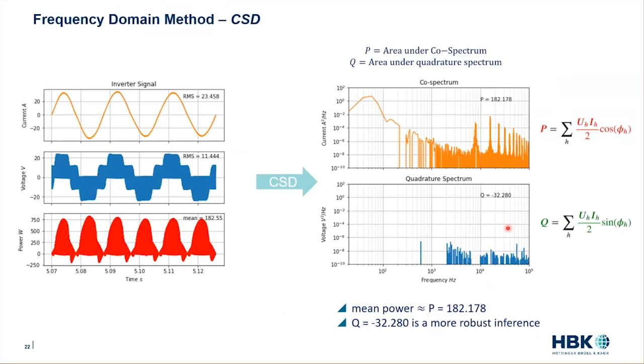So when you apply a non-sinusoidal function, what it does is it smudges all the frequencies together into one number, and therefore it can overestimate reactive power. But the other one, we keep those frequencies separate in the frequency domain, so therefore when we multiply them together, we end up with a much more robust inference of the reactive power.